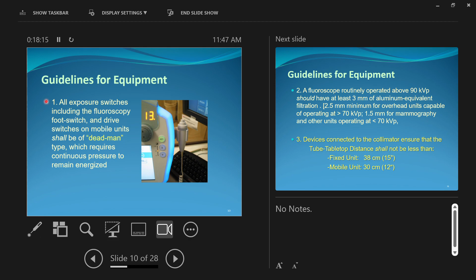Guidelines for filtration. So, good. We mentioned what filtration was. It's a piece of aluminum usually placed in the path of the x-ray beam that stops low energy x-rays from getting out of the x-ray machine. In fluoroscopy, which we don't do, but let me read it, any machine operating above 90 kVp has to have 3 millimeters of aluminum or aluminum equivalent. You can use anything as long as it's equivalent to 3 millimeters of aluminum.